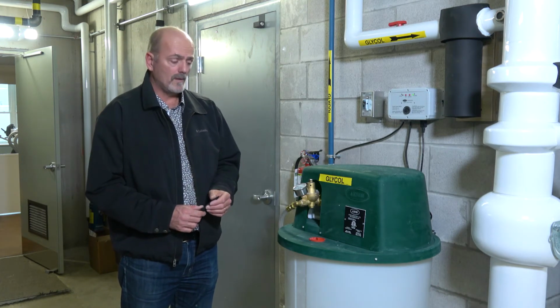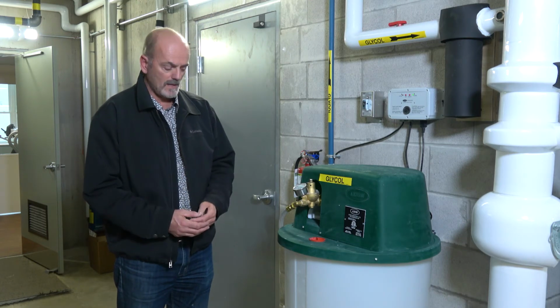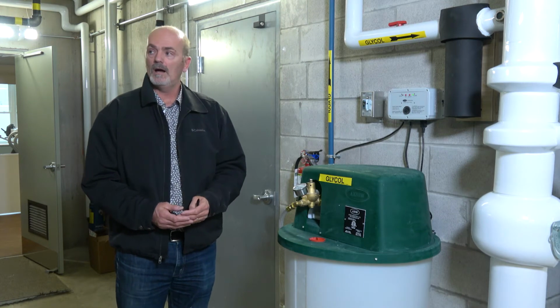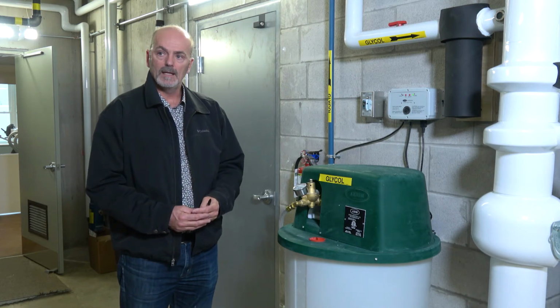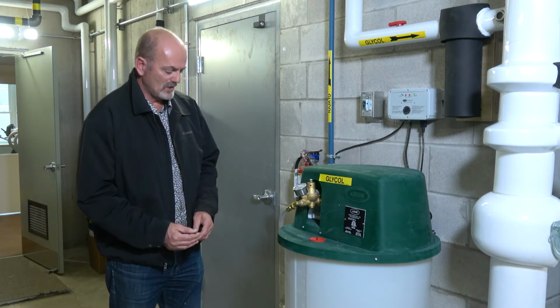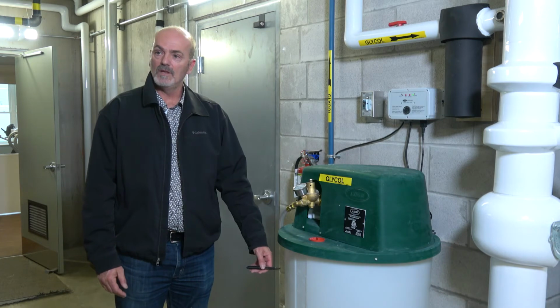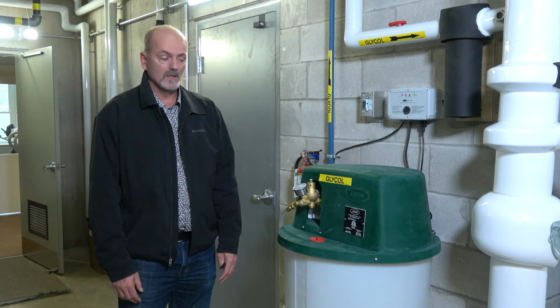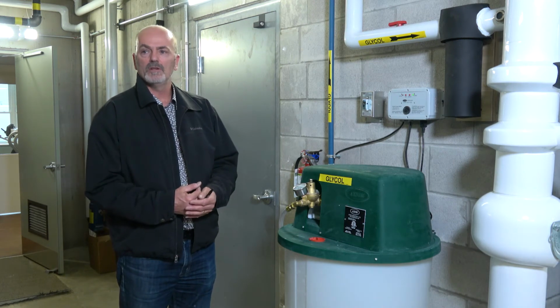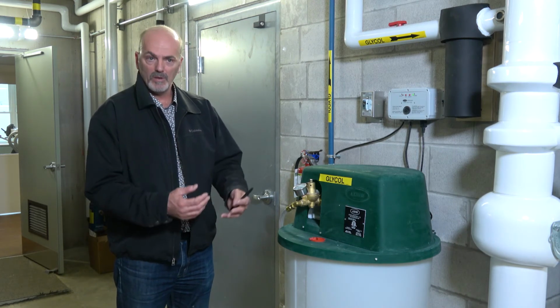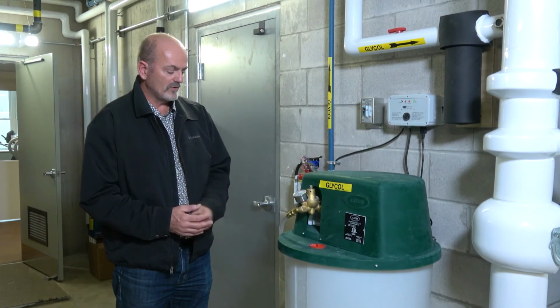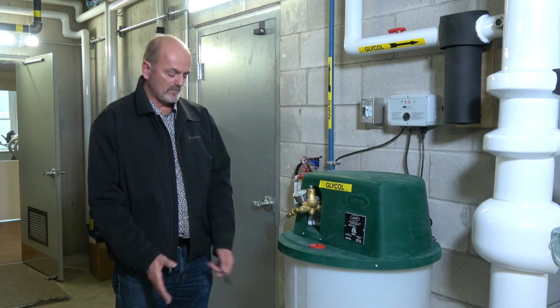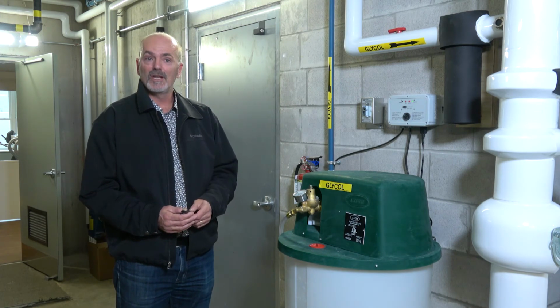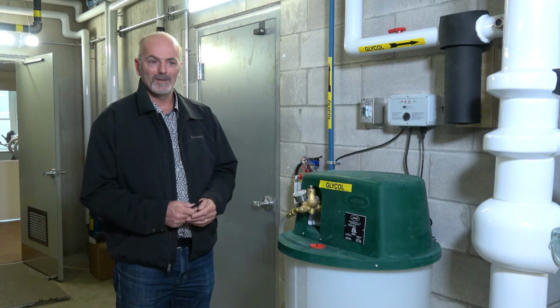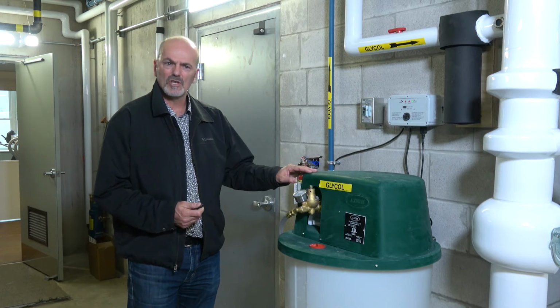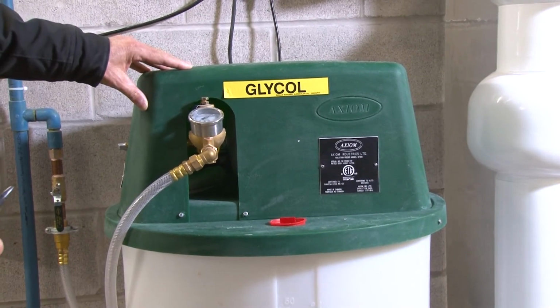If the condition continues and you keep emptying the tank, it's an indicator that you have a leak somewhere in the system and you need to address it. My recommendation is, I know Keith and Mackenzie Mechanical will leave this with a level in it that they're comfortable with, so that now that the system's been running for a period of time and most of the air is out of the system and has been replaced with a pre-mixed water and glycol, they'll leave a certain level in here, and if it empties itself out and that alarm goes off, that's an indicator you have a leak. But we know the chances are in this system, on the chiller side, right? On the chiller side, there's probably not going to be a leak.